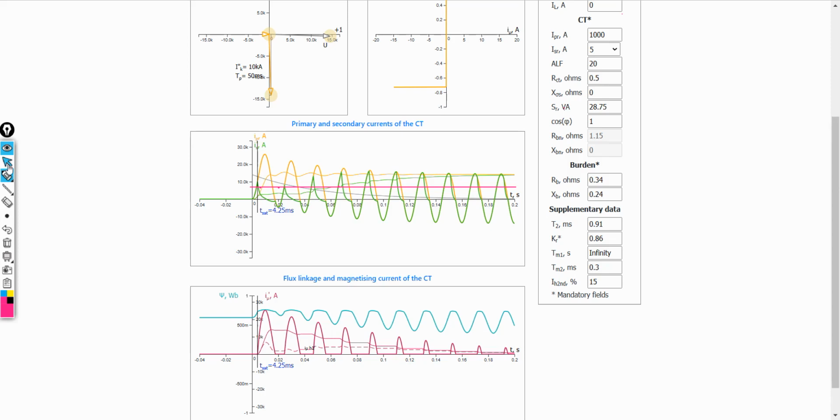The technical report IEC 61869-100 only limits itself to the specification of T-AL, the time until the accuracy limit on the basis of which the transient dimensioning factor KTD for the manufacturing of the current transformer is calculated. This time is essentially the same as the saturation time Tz, specified in our model.